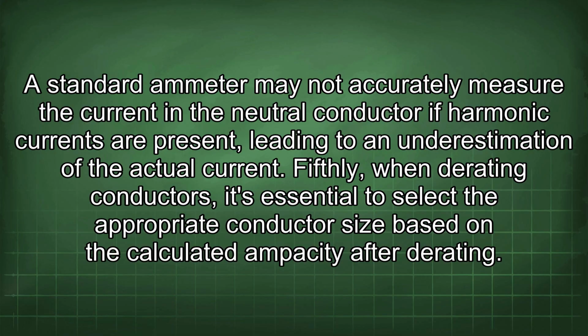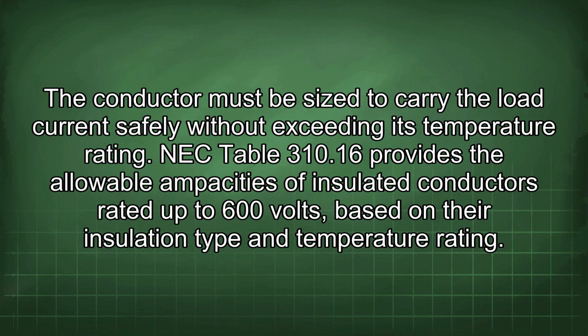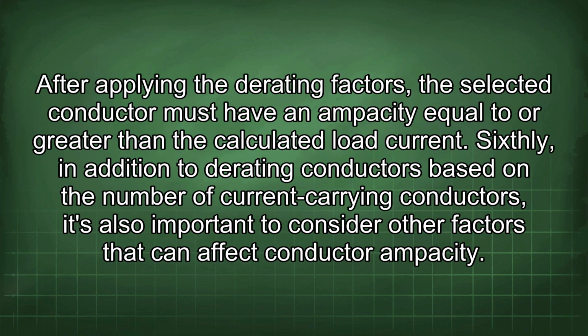Fifthly, when derating conductors, it's essential to select the appropriate conductor size based on the calculated ampacity after derating. The conductor must be sized to carry the load current safely without exceeding its temperature rating. NEC Table 310.16 provides the allowable ampacities of insulated conductors rated up to 600 volts, based on their insulation type and temperature rating. After applying the derating factors, the selected conductor must have an ampacity equal to or greater than the calculated load current.